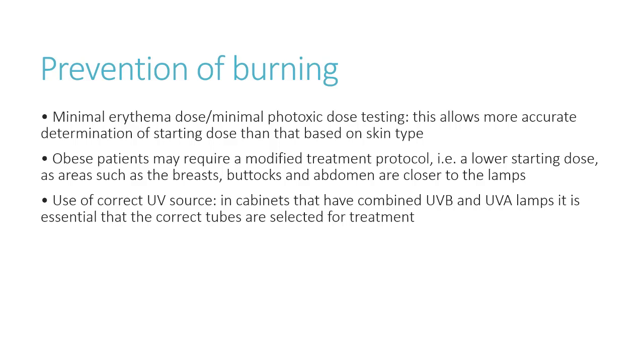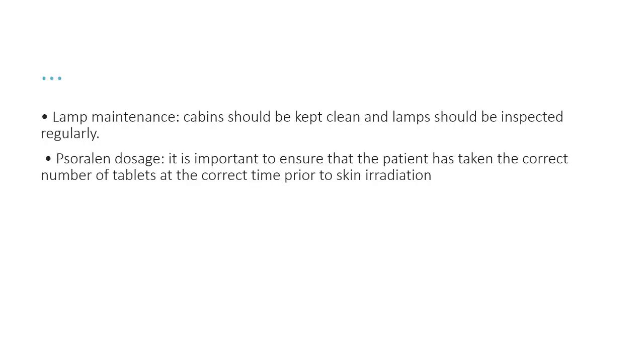To prevent burning risk: minimal erythema dose or minimal phototoxic dose testing allows more accurate determination of starting dose than skin type alone. Obese patients may require a modified protocol with a lower starting dose, as areas such as the breasts, buttocks, and abdomen are closer to the lamps. It is essential that the correct UV source is selected in cabinets with combined UVB and UVA lamps. Lamp maintenance is important — cabins should be kept clean and lamps inspected regularly. Psoralen dosage must be verified to ensure the patient has taken the correct number of tablets at the correct time prior to irradiation.